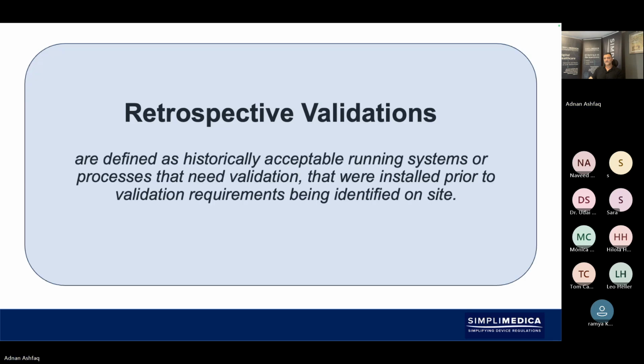So that's also fine. I spoke earlier about retrospective validation. Retrospective validation is a term which isn't usually favored by the FDA, because it's usually misunderstood to mean that we can accept validation from retrospective batches that have been manufactured. That's not acceptable. What is acceptable is, if you have a piece of equipment which has been running historically, you would need to run the validation as if it was a new system. That's what's meant by retrospective validation. And this happens all the time. You have an authority or an auditor that's come in, and they've raised a non-conformance because equipment was not validated or was inadequately validated, for equipment that's been running historically for a number of years in the factory. So then you have to revisit this and look at it as retrospective validation.